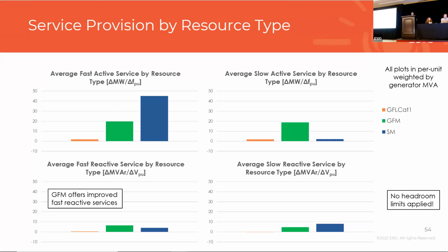The GFM resource plant that we modeled here does not have a plant controller; we assumed it's just the inverter. If a GFM plant also has a dead band at the plant controller level, or a load following controller at the plant level, it's going to bring the response back down, and you lose that service in the longer time frame. This is where the time-dependent nature of the service becomes important in how we look at system performance.